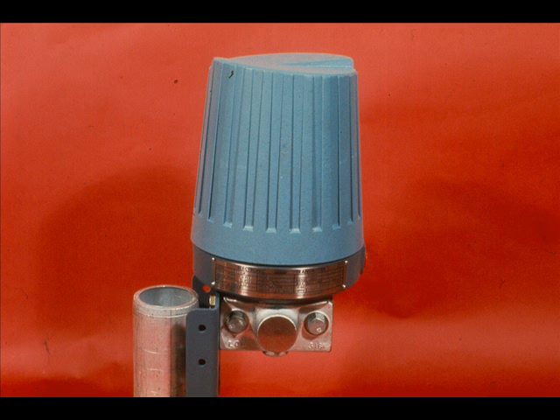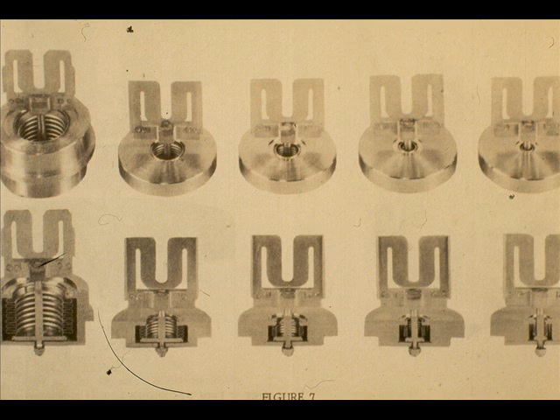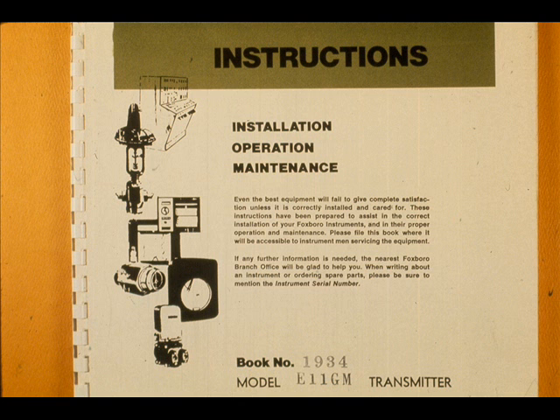We will next change the range and calibrate a Foxboro E11GM pressure transmitter. The procedure will be very similar to that used for the E13 differential pressure transmitter. The pressure transmitter range can be changed to any value within the limits of the capsule. Consult the instruction manual for specific capsule limitations.